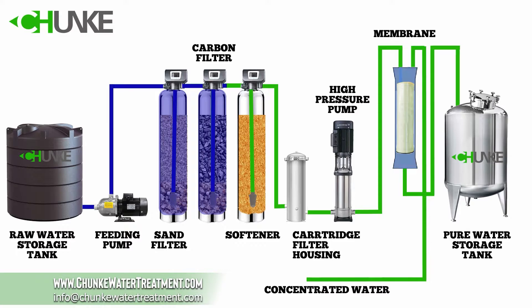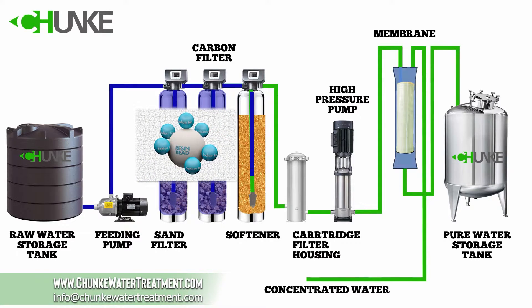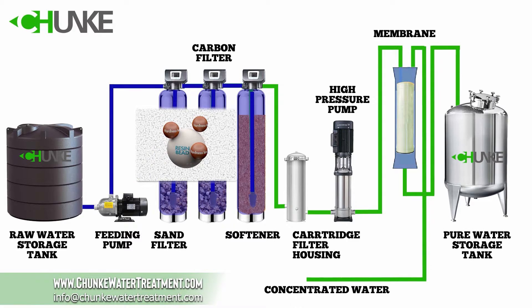Third, water goes to the water softener to remove hardness. There is ion exchange resin in the softener tank. The ion exchange resin exchanges sodium with calcium and magnesium, which are the minerals that give hardness to water.